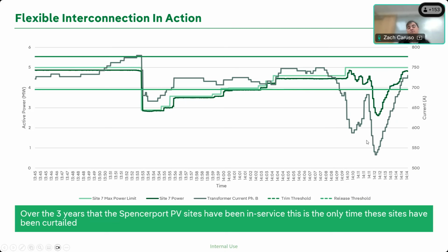Once that cloud goes over, all the flexible PV, as well as all the other PV on the circuit that's not flexible, drops its output, and the current flow through the bank drops precipitously as well. When that happens, we say, okay, you guys can go back to full output from your PV sites, because we don't need to be curtailing you anymore. There's plenty of capacity for you to use. And ignore this, this is out of date. They have actually been curtailed more than this.